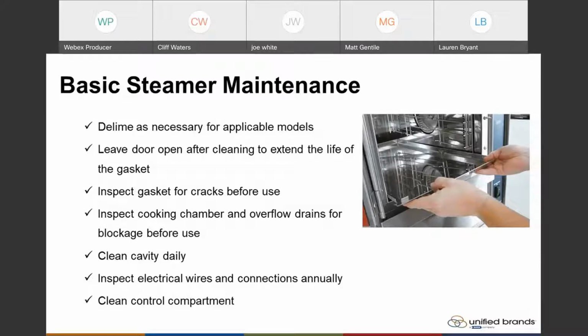If you happen not to wipe the unit out daily, you'll start to get a powdery limescale buildup inside the reservoir. At that point, as noted in our operator manual, you can use white vinegar to clean your unit - just pour in a cup of vinegar, turn the unit on, and let it go through a cycle. It will break down the limescale and flush it out of the drain.